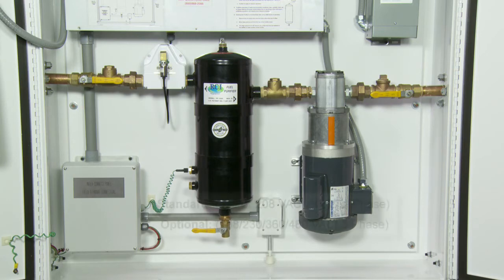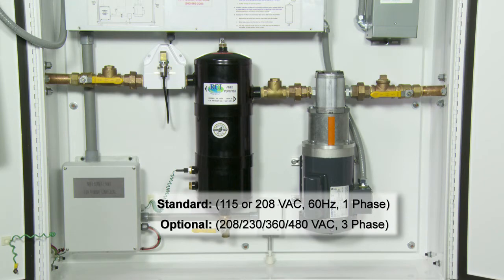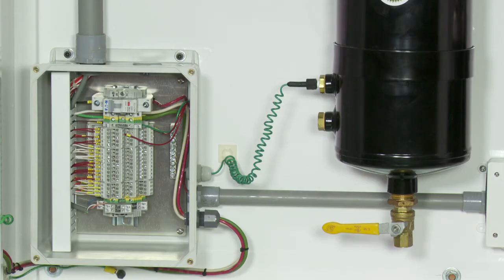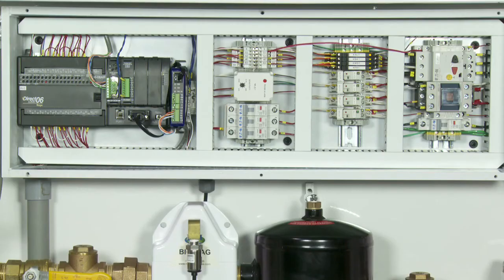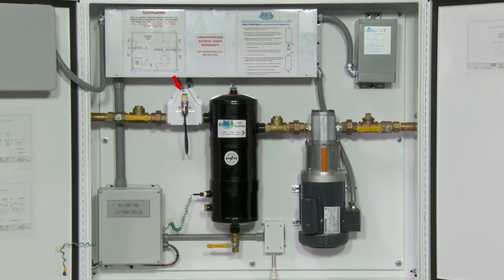The electrical input here includes a standard 115 or 208 volt AC 60 Hz single phase power or an optional 208, 230, 360, or 480 volt AC 3-phase power. The outputs include a standard alarm communication with 4 relays, including general alarm, programmable relay, water purge, and leak detection. Plus, there are also additional communication options available using Modbus RTU, BACnet, or Ethernet communication, an analog pressure transducer with factory settings of 5 psi for low pressure and 75 psi for high pressure, and a microorganism decontamination unit, or biomag.